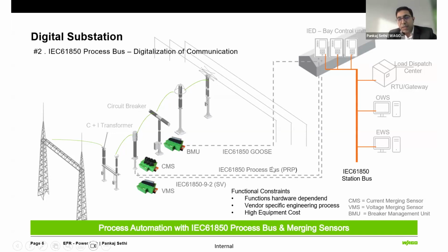This technology has helped eliminate copper and its related costs and maintenance issues. But some issues remain - it's still hardware dependent, so you still need IEDs in the control room to make decisions for protection of the electrical network. It also remains very vendor specific, since buying an IED from one particular vendor means your entire engineering process has to align with that vendor, increasing equipment cost.